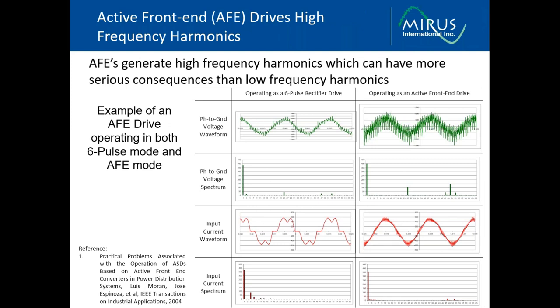This case study shows an application on a marine vessel. It's taken from a published IEEE paper. In this application, the variable speed drives that were used were AFE drives, but they could be configured to operate as a simple six pulse drive, to simulate a rectifier operation. So the authors of the paper ran it in both modes. Here we can see measurements taken from the phase to ground voltage waveform. When it's operating as a six pulse rectifier, there is no obvious high frequency noise on that waveform. But when the same drive is operated as an active front end, this is substantially increased.